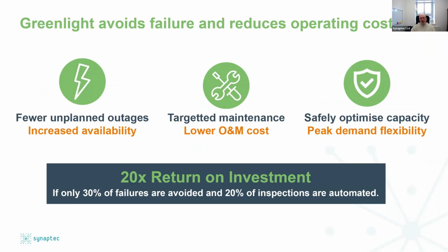Now, when we deployed this on, for example, one of the world's largest offshore wind farms, and we're looking at thousands of sensors and hundreds of cables operating over 25, or I think it's 30 years of operational life, the investment consideration is significant, because we are fundamentally de-risking that wind farm operation, and they know that they'll have cable failures over the lifetime of that array. And when you calculate how many there are likely to be, maybe 10, maybe 15 is a reasonable number in offshore wind, even today, with all of the focus that's been put into installing them correctly and trenching them correctly and operating them correctly. There are still a lot of unplanned, unscheduled failures. If you can avoid even the first one of those, let's say 10 failures, the system will pay for itself.